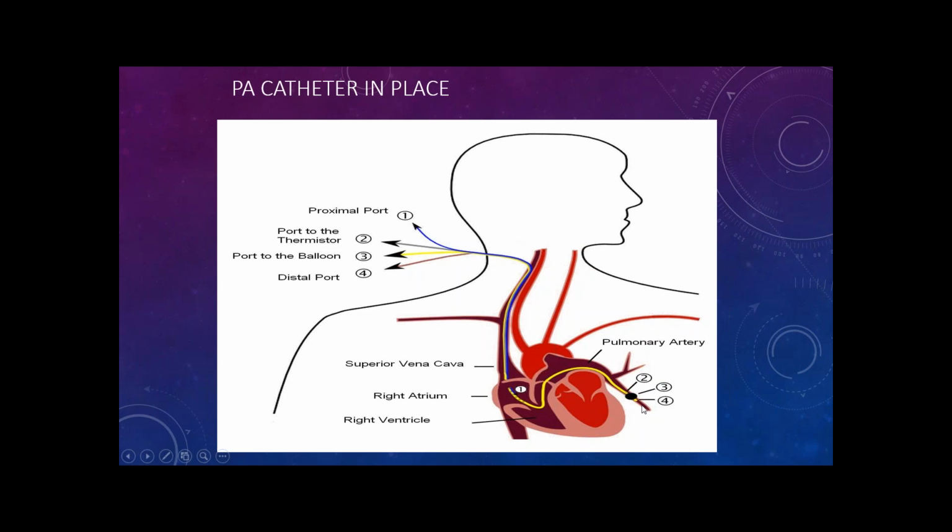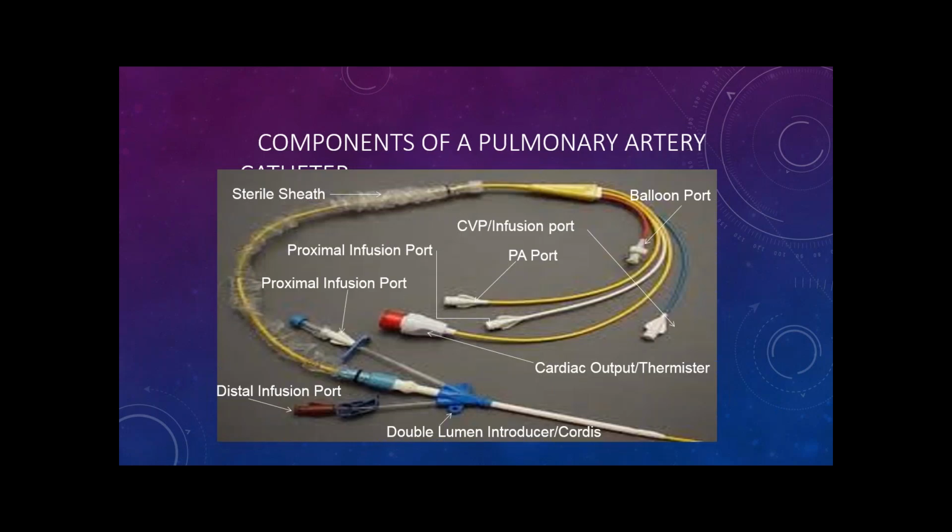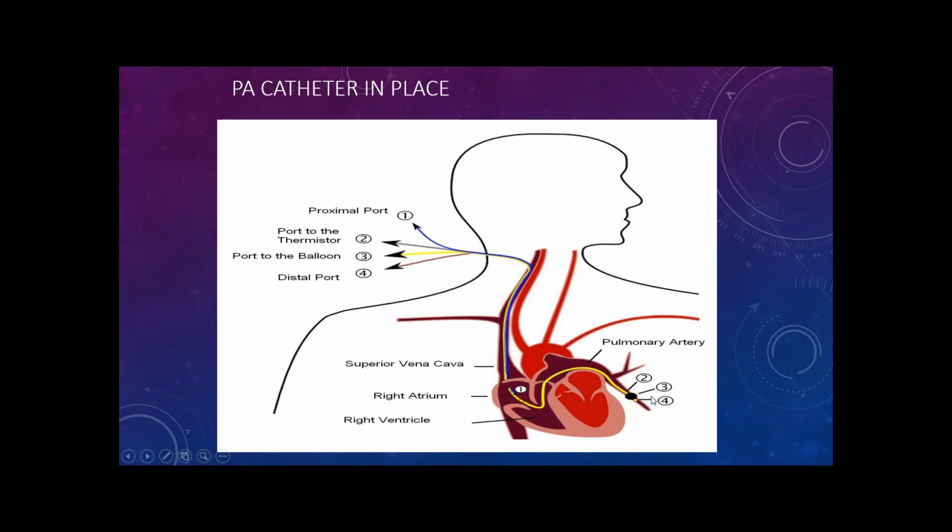There is a thermistor down here. It's actually coiled copper, and it goes with this port here, the cardiac output port, and it gives you the opportunity to have continuous readouts of the temperature, just as much as getting continuous readouts of cardiac output. Okay, just to give you a little bit of an idea of what it might look like and exactly how things are working.